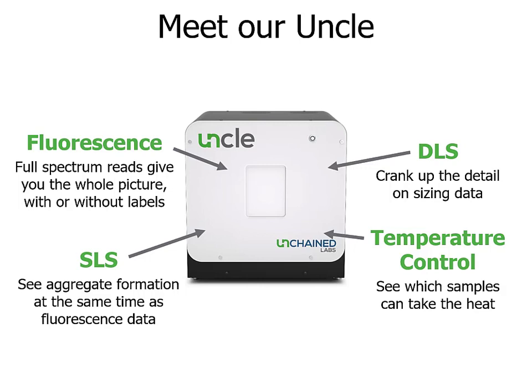Lastly, UNCLE contains very precise temperature control and therefore can use any of these three methods either during a thermal ramp, isothermally, during a stepped ramp, or really any sort of heating design you can possibly imagine.